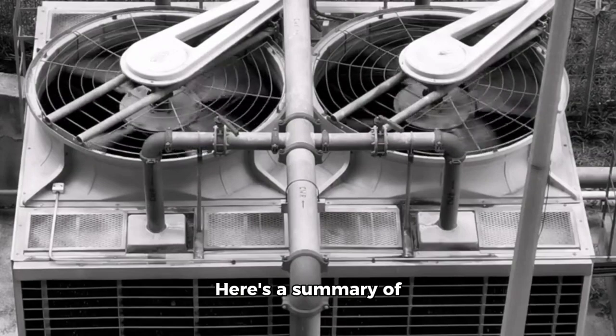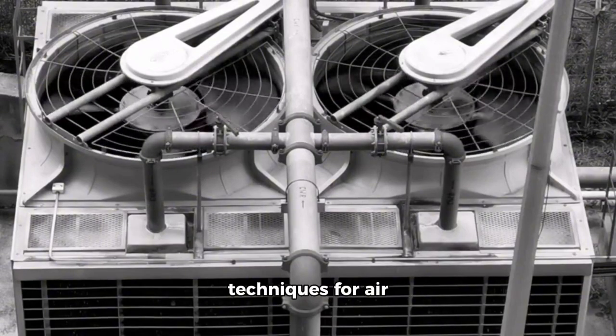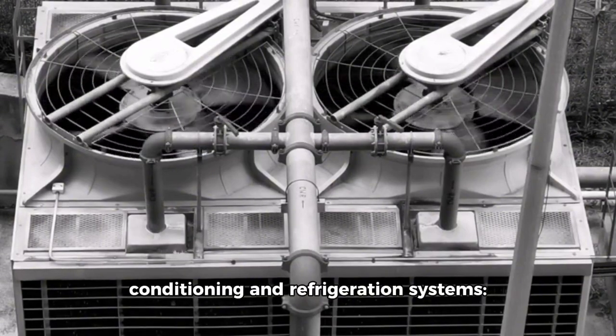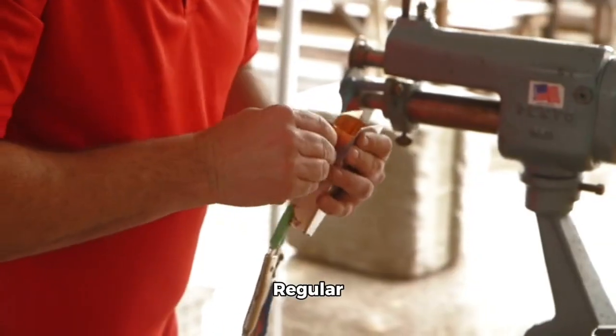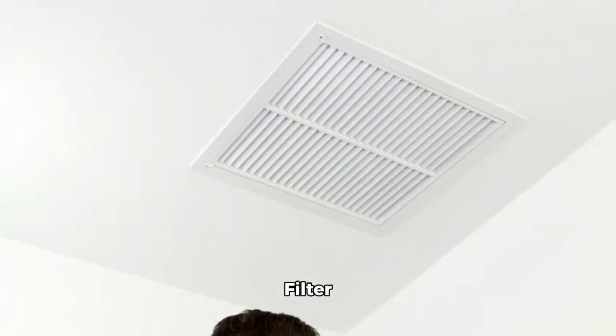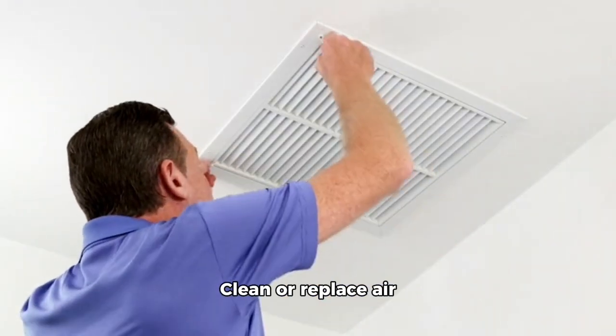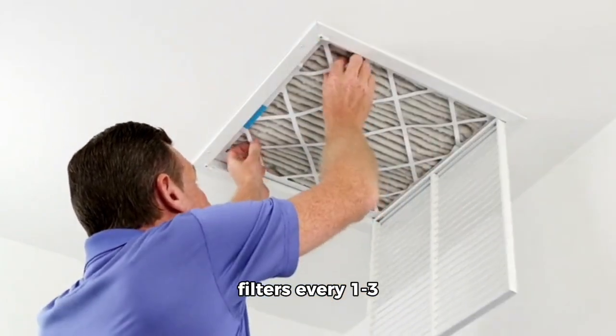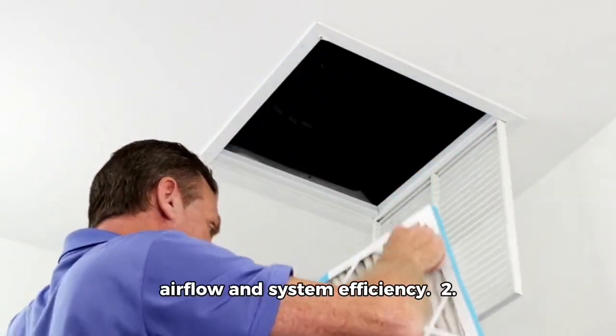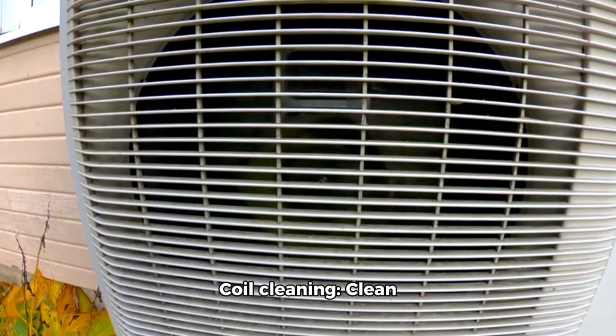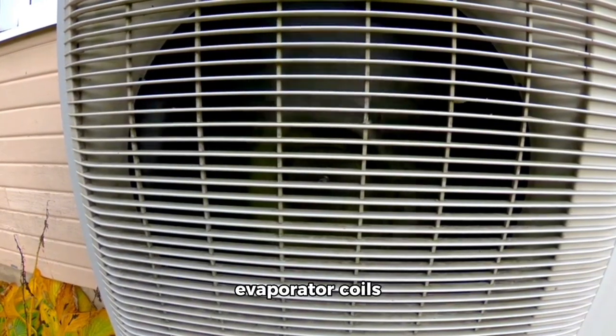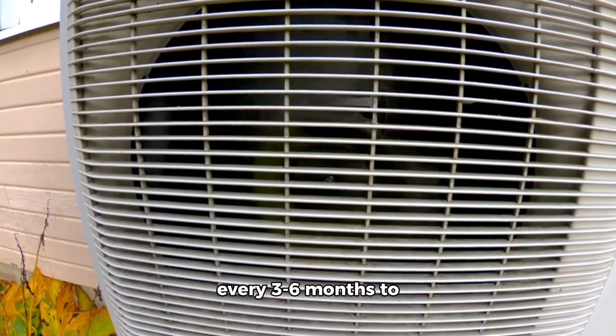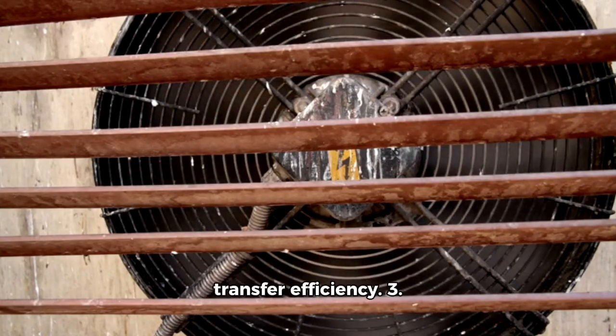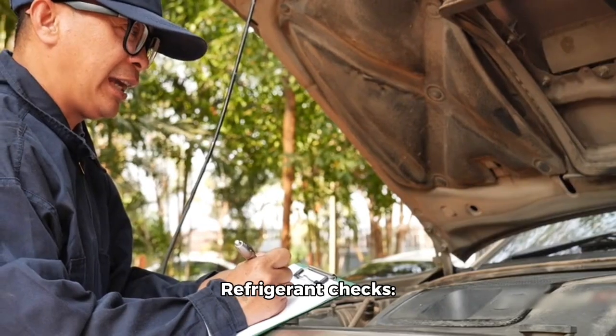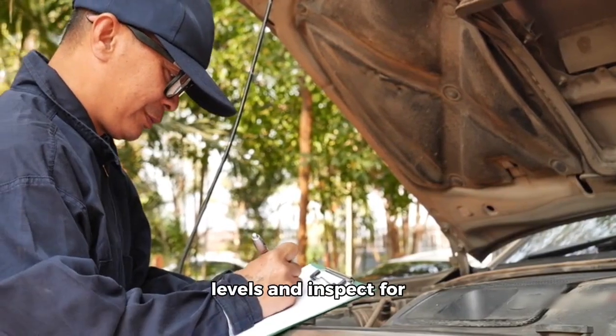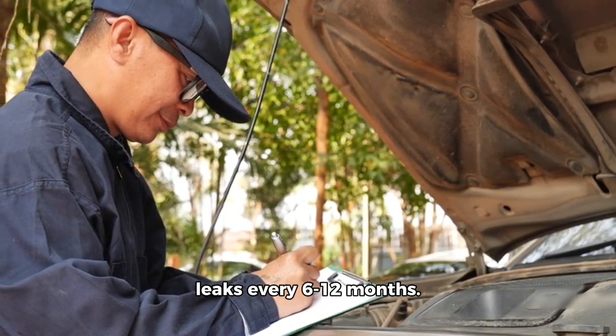Here's a summary of preventative maintenance techniques for air conditioning and refrigeration systems. Regular maintenance tasks. 1. Filter cleaning or replacement. Clean or replace air filters every 1 to 3 months to ensure proper airflow and system efficiency. 2. Coil cleaning. Clean condenser and evaporator coils every 3 to 6 months to maintain heat transfer efficiency. 3. Refrigerant checks. Verify refrigerant levels and inspect for leaks every 6 to 12 months.